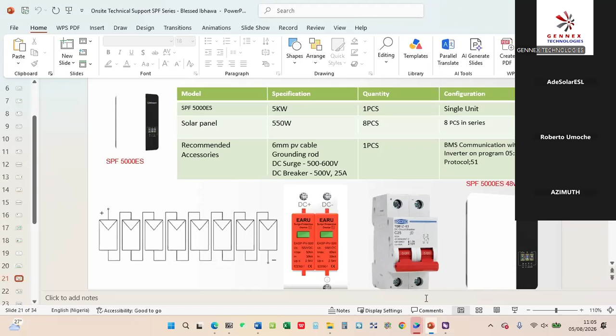Next slide. On the grid side, you should get a surge, an AVR, and a breaker. The reason for adding an AVR is to protect against a blast on the transformer, which is not under your control, it's something that just happens. What helps in this case is those two devices at the front, to ensure that if the incoming voltage is quite high, they disengage and save you the stress of machine damage. This is really, really encouraged.